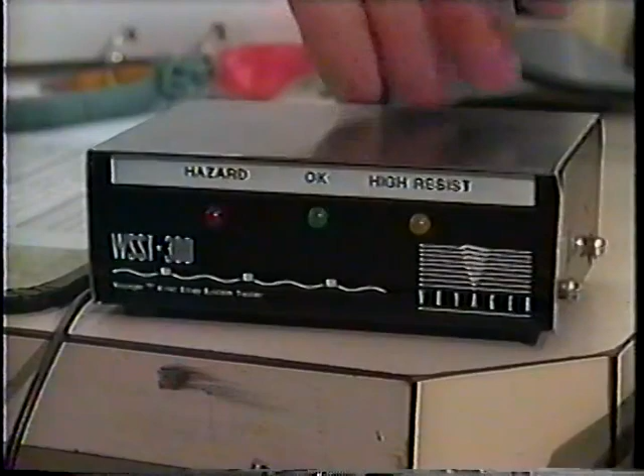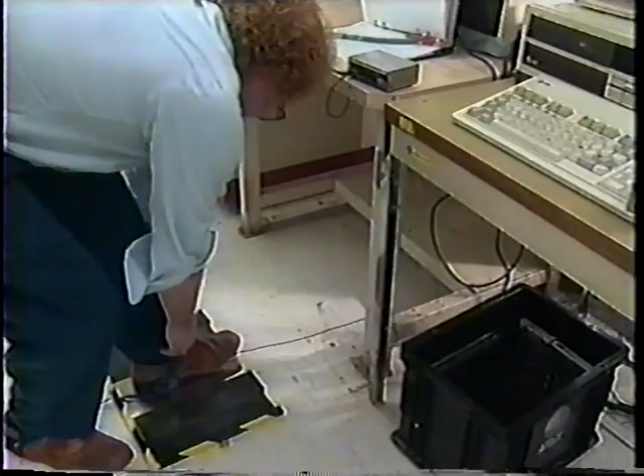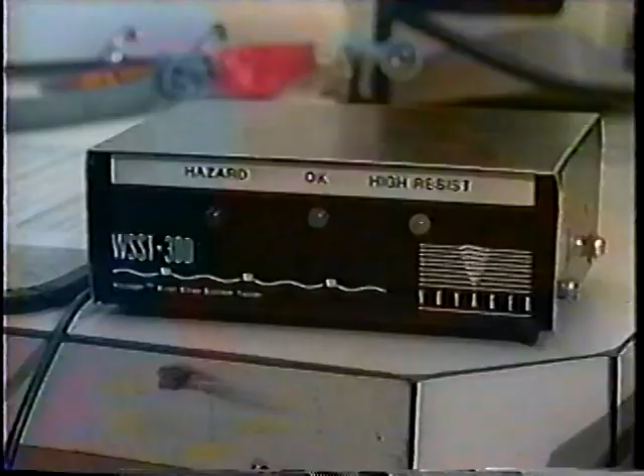You should test your electrostatic discharge protective footwear at least once a day at the beginning of your shift. Hold the footwear tester with your hand while standing on the test plate. Test each foot separately. If the yellow light comes on, you are not wearing good footwear or your footwear is on wrong. Check to see what the problem is and correct it. Don't go into the ESD protective area until the green light on the tester comes on. If the red light comes on, your shoe grounders are too conductive. While you are not an ESD hazard, you cannot work around exposed hazardous voltages.